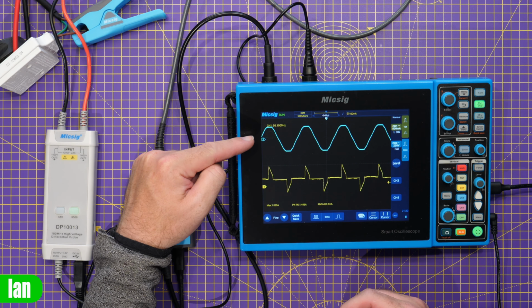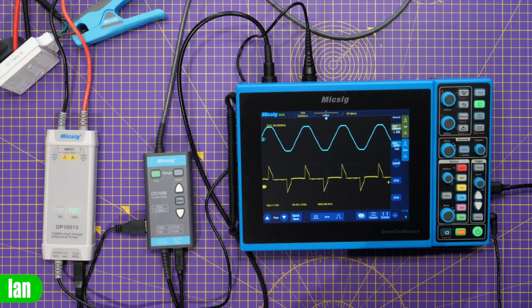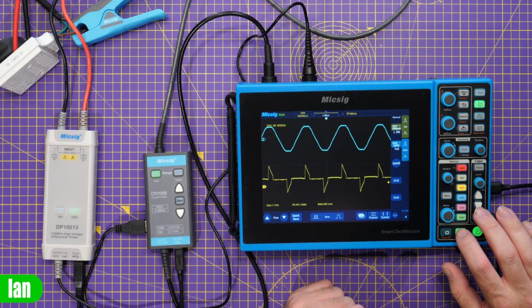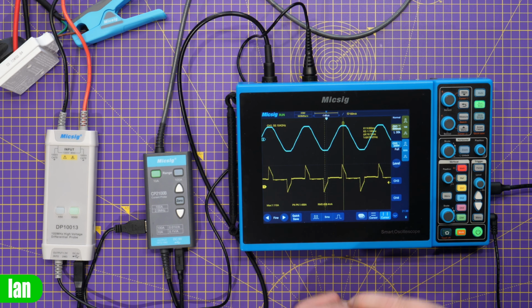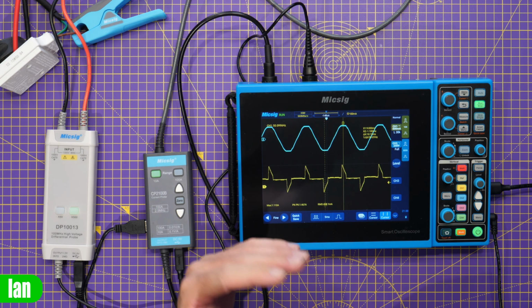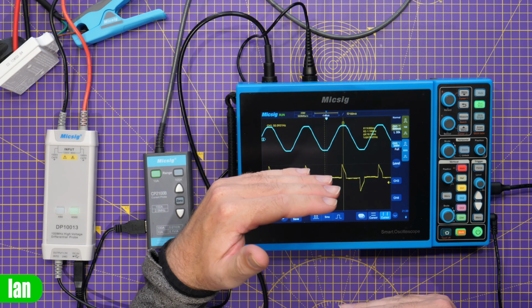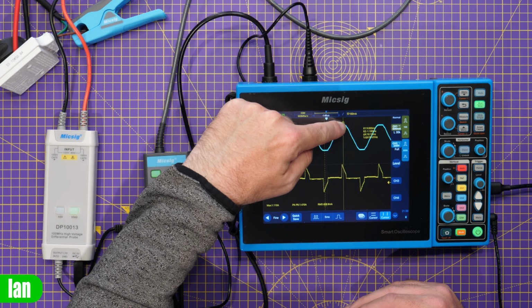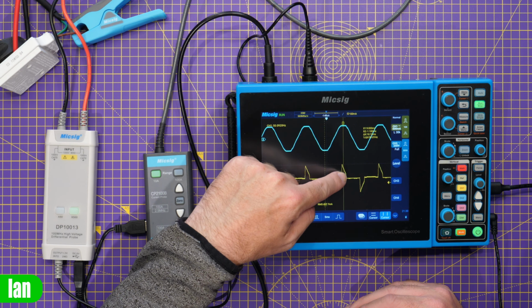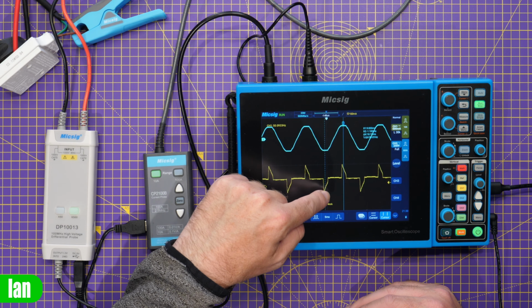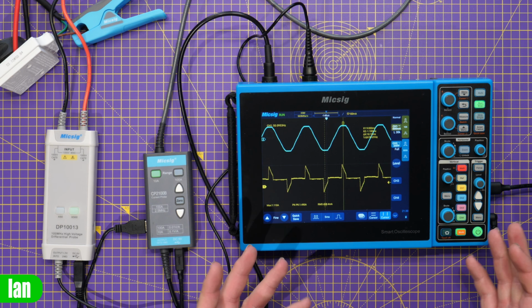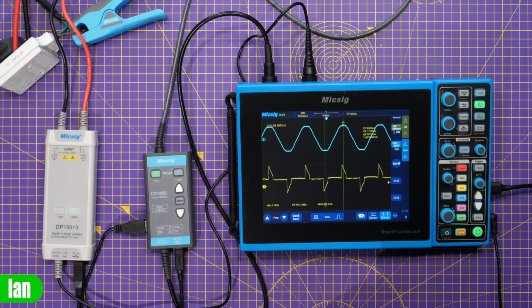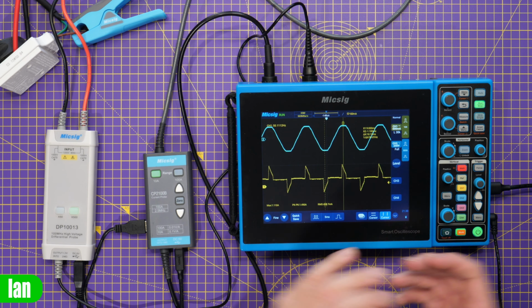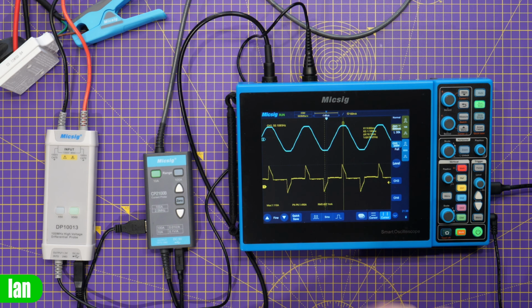We have our voltage at the top in blue and our current at the bottom. The nice thing is, you can see they are both aligned. So if I just turn on the cursors a second, you can see if we look at the peaks of the waveforms, they are aligned with each other. So for instance, the peak of the voltage is aligned with the peak of the current. The lower point of the voltage is aligned with the lower point of the current, which means the voltage and current are in phase. You could say that the load that we have on here has a good power factor because they are basically aligned.